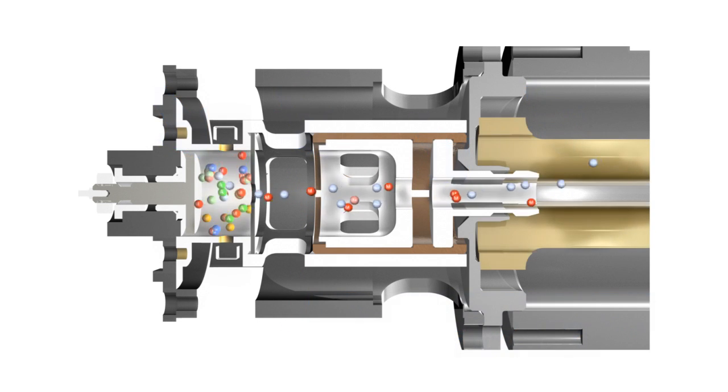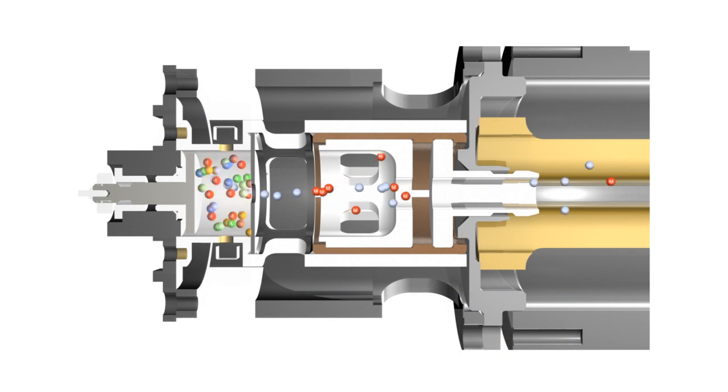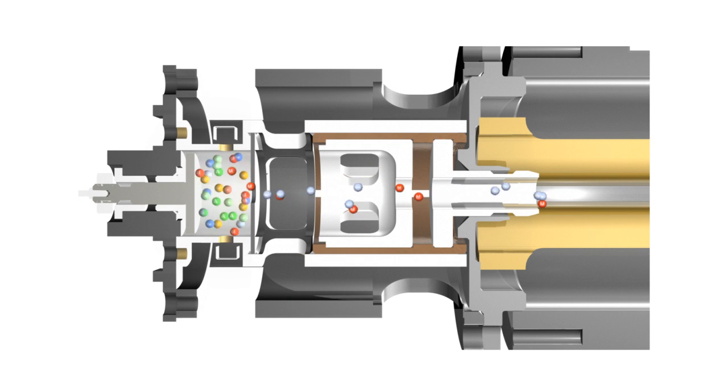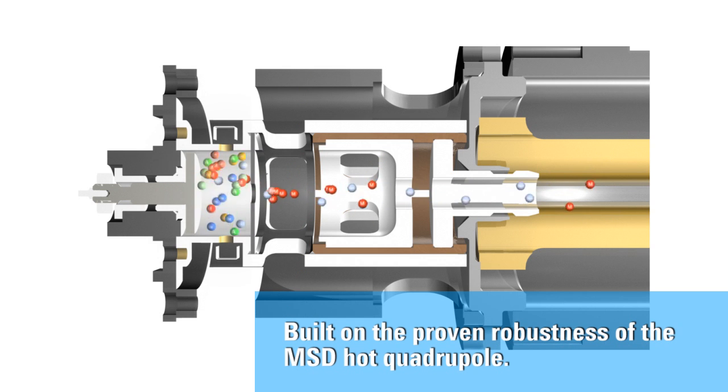The Agilent 7000A uses a combination of proprietary and patented technologies to avoid contamination problems and ensure robust, high performance operation. These include an inert source operating at up to 350 degrees Celsius, and quartz quadrupole operating at up to 200 degrees Celsius. With 35 years of MS experience, Agilent built the 7000A around the unique hot quartz analyzer of the MSD, not the cooler metal quadrupole rods used for LC-MS-MS.